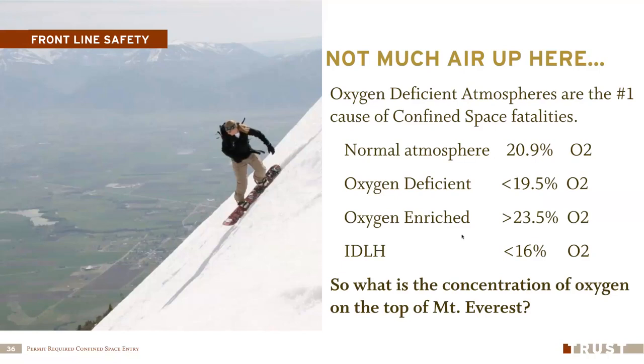There's another special level we talk about, the IDLH, or immediately dangerous to life and health concentration. Anything less than 16% oxygen, you could die, be disabled, or not be able to get yourself out of that environment. So the window we look at is between 19.5% and 23.5% oxygen. But I want to be dead on 20.9% oxygen - I want to ventilate the space until it's at natural concentration, because if I'm at 19.6, I know I'm very close to being oxygen deficient. I want to ventilate the space and make it safe to go in.